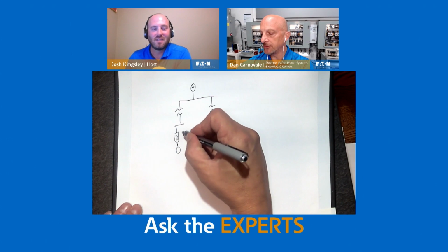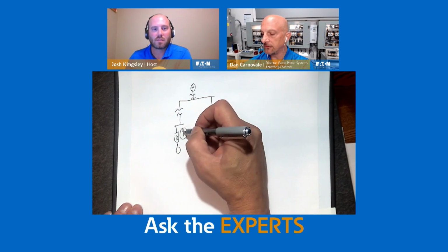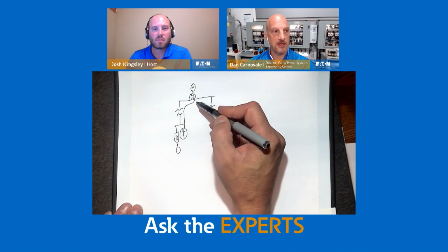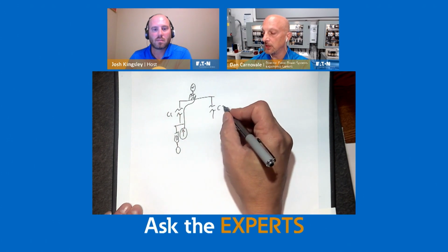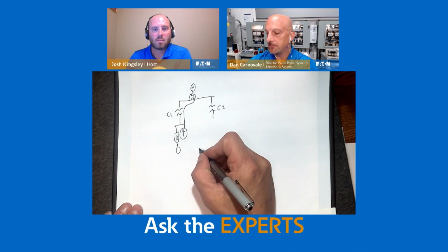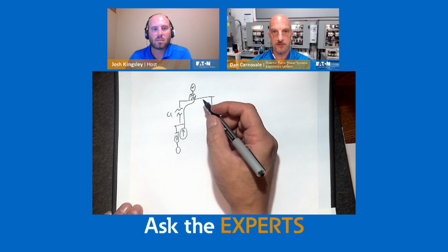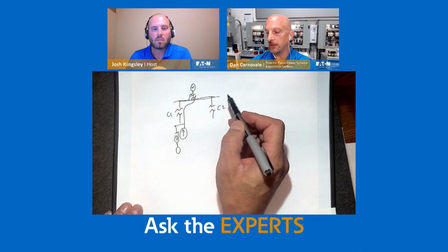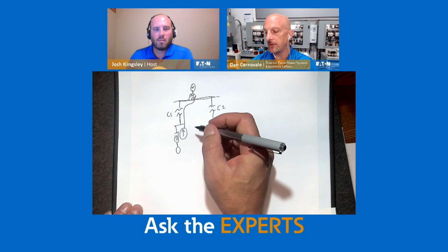So as these harmonics come out of this system here, again, there's always transformers back through the system. So if this current is affecting this transformer, it might actually cause damage to that, and this customer could see it. So this is customer one and customer two. So there's tables in the IEEE 519 standard that basically define the current distortion that you're allowed to push up through your system and the voltage distortion that you're allowed to create at the common point, at the point of common coupling. So sometimes it's on the primary of the transformer, sometimes it's on the secondary, depends.